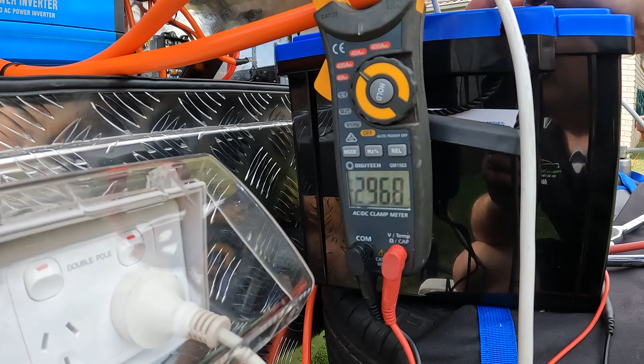So I don't have this problem because I'm running a battery bank. Down there with the battery bank, I don't see much voltage sag because there's a lot of batteries there. But I think what's happening is it's going into low voltage disconnect on the inverter. I was checking before and it was only going down to 12.6 when I hit 300 amps, but that must be enough to maybe trip this inverter out.